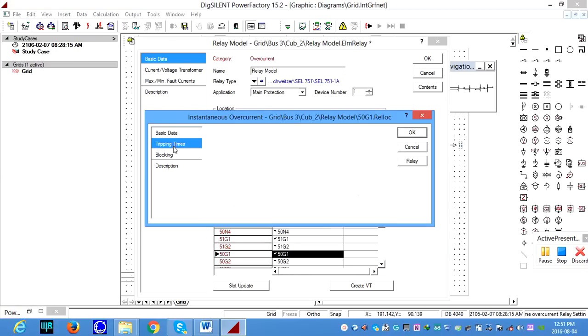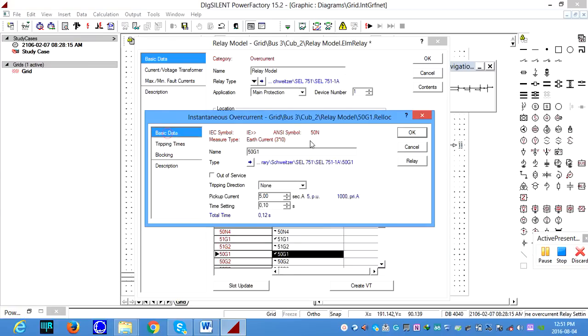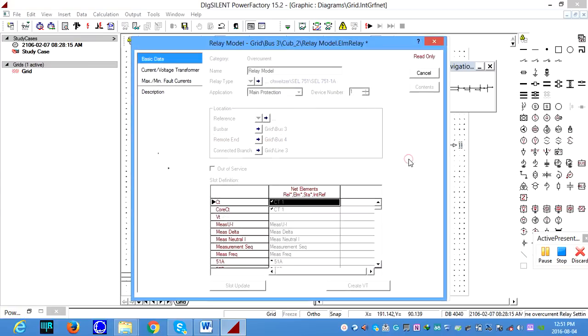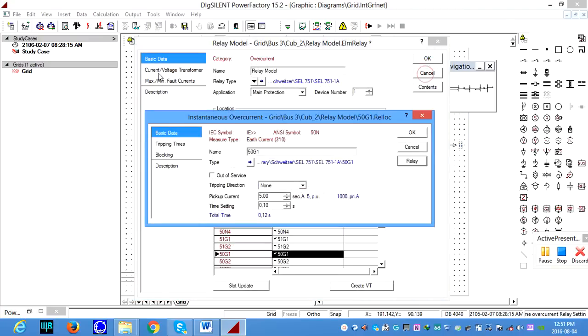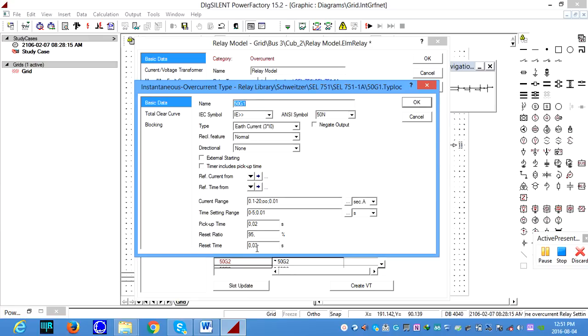I think we can see this from these basic options. If you go to these relay options, I think it's here somewhere. Okay, if you go here, you can see the pickup current, time setting 0.2 seconds is a default. If you want to change, this is the ratio that gives the minimum and maximum range for the current setting and the time dial setting.